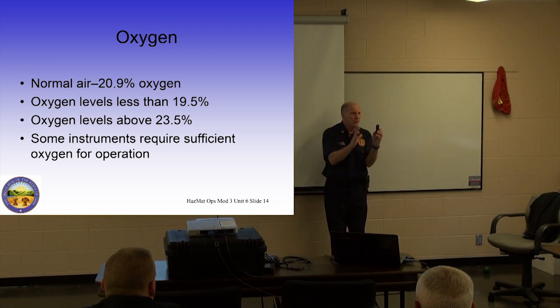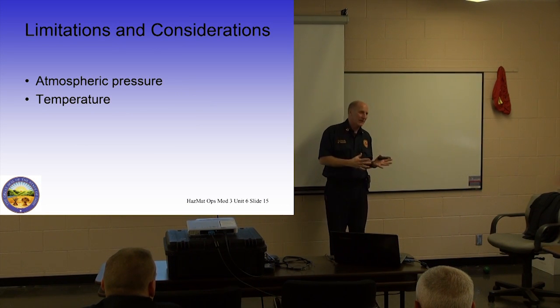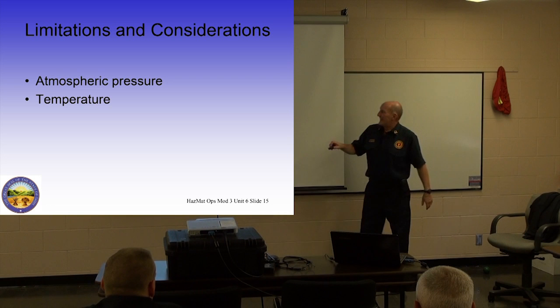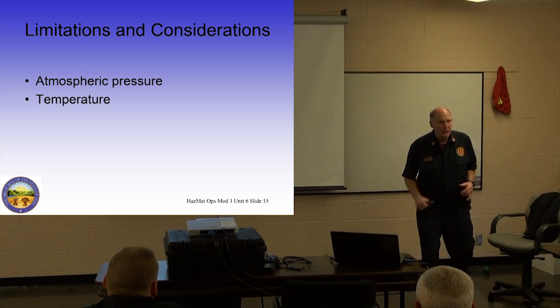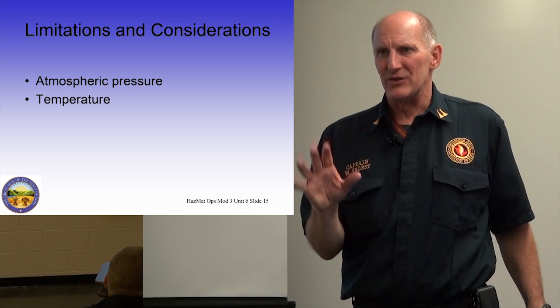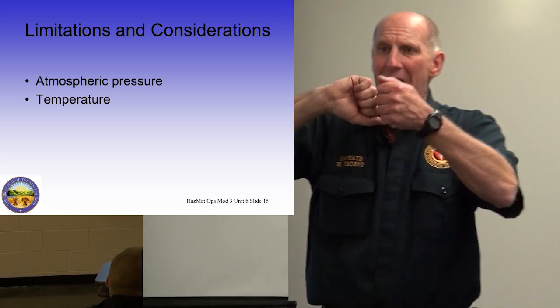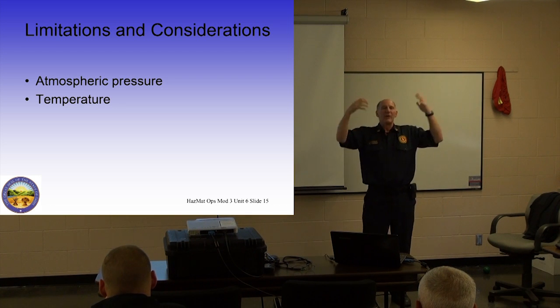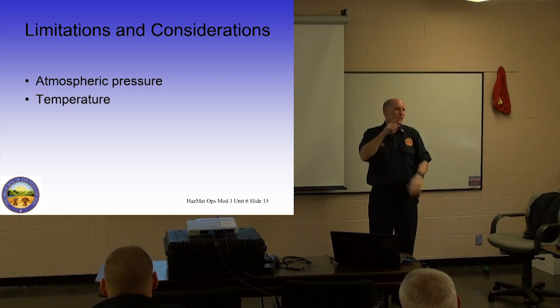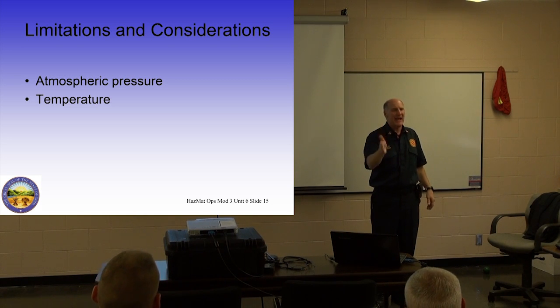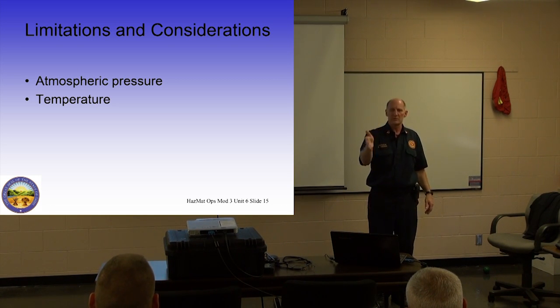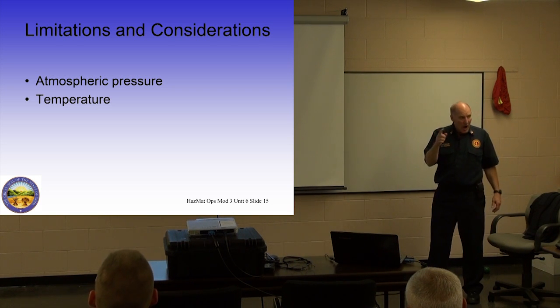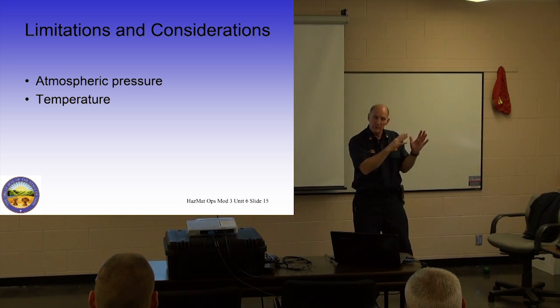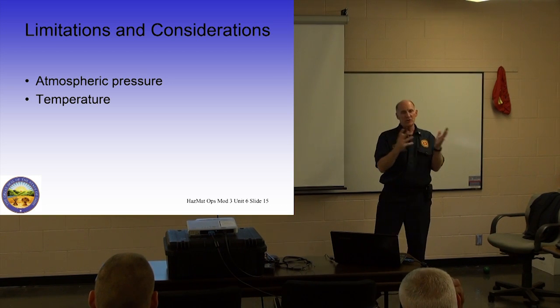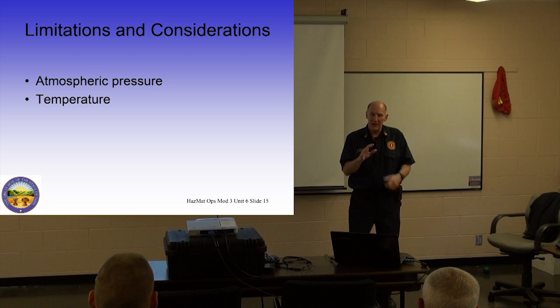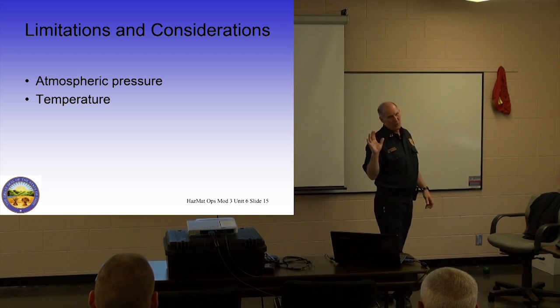Instruments require the O2 to be in that normal area to be accurate. So remember, the idea behind it is O2. It can be adjusted. The way it works is two chemicals that react much like a battery. And when they're at normal O2 and normal temperature, they're going to react at a certain speed. And if they're reacting at that speed, the oxygen level is considered 20.9. But when oxygen drops, they react slower, and the computer gives you lower numbers. When the oxygen increases, they react faster, and the computer gives you higher numbers. That's the way it works.